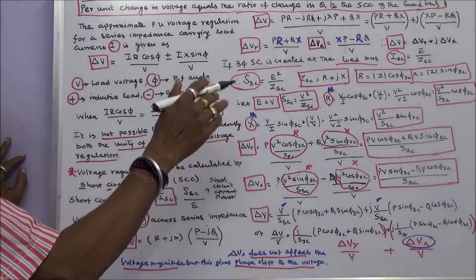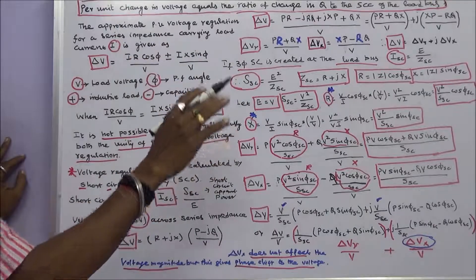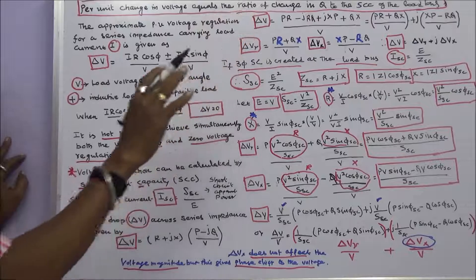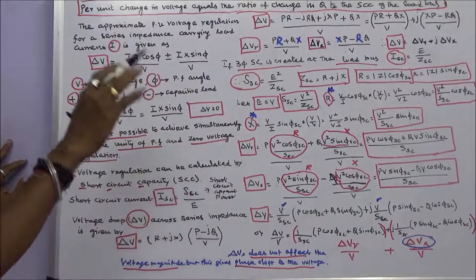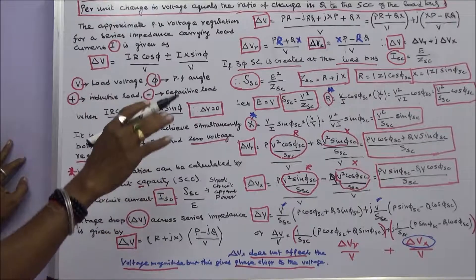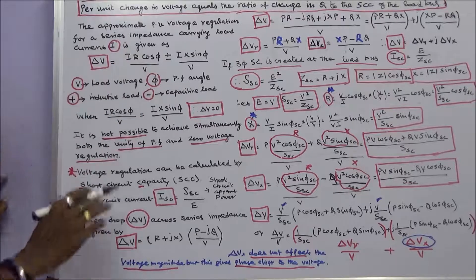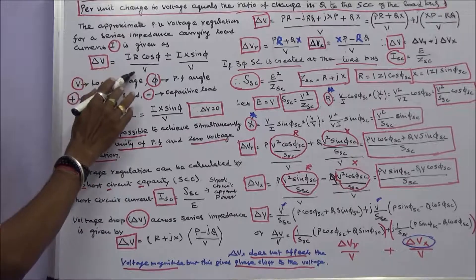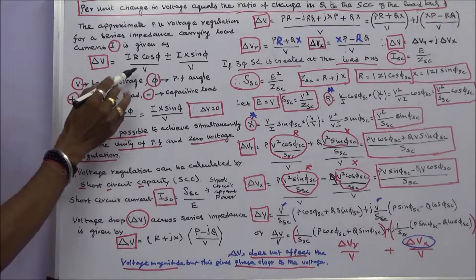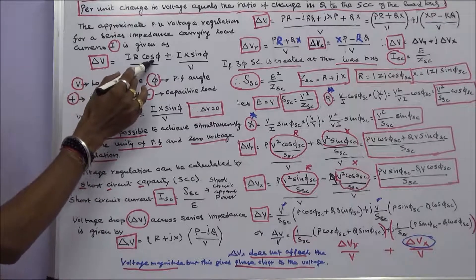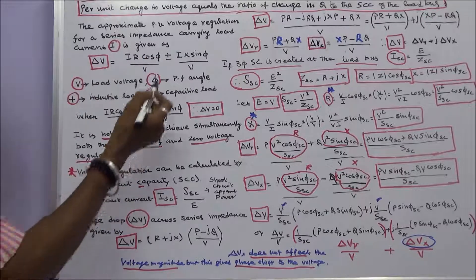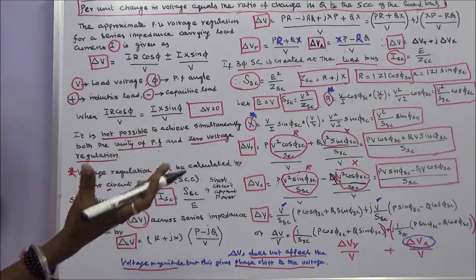In this class we discuss that per unit change in voltage equals the ratio of change in reactive power Q to the short circuit capacity of the load. The approximate per unit voltage regulation for a series impedance carrying load current I is given as: delta V equals IR cos(φ) / V plus or minus IX sin(φ) / V, where V is the load voltage, φ is the power factor angle. The plus sign indicates an inductive load that consumes reactive power; the minus sign indicates a capacitive load that generates reactive power.